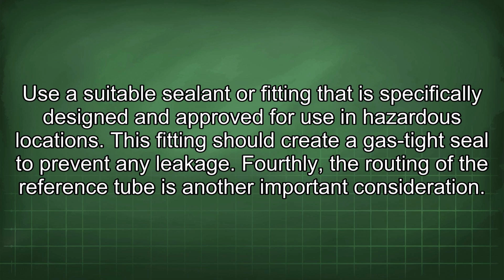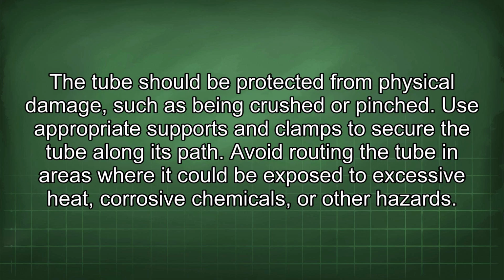Fourthly, the routing of the reference tube is another important consideration. The tube should be protected from physical damage, such as being crushed or pinched. Use appropriate supports and clamps to secure the tube along its path. Avoid routing the tube in areas where it could be exposed to excessive heat, corrosive chemicals, or other hazards.